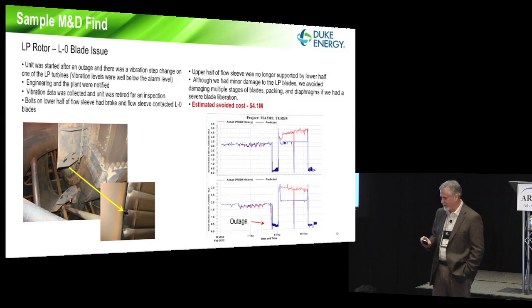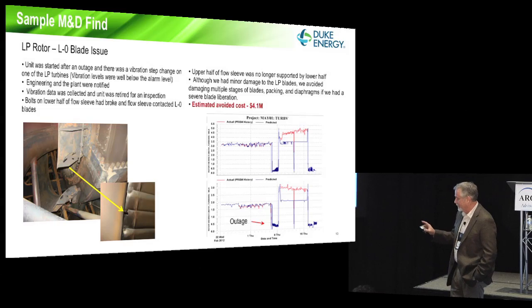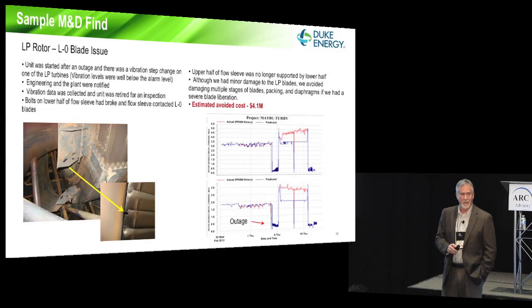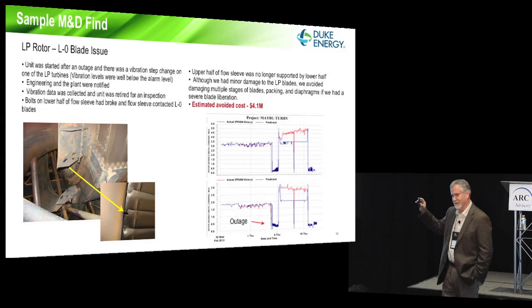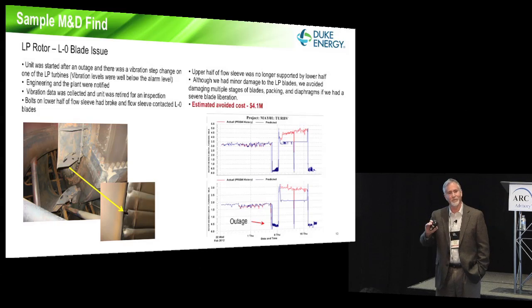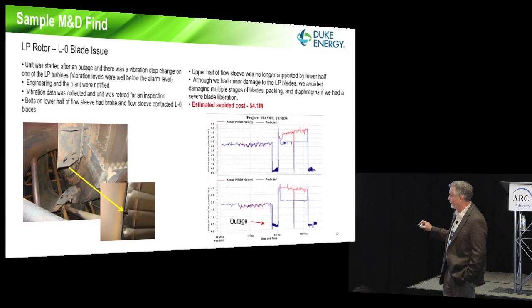Our center picked this up and notified the engineers in the plant that something didn't look right. What we were looking at was subsynchronous information - something we'd never have seen without the advanced sensors and diagnostics on the turbine, because overall vibration alone wouldn't have moved. This was really key for us. It turned out to be a flow sleeve, which directs steam flow inside the turbine - bolts had come loose, and the edge of it had nicked the blades.